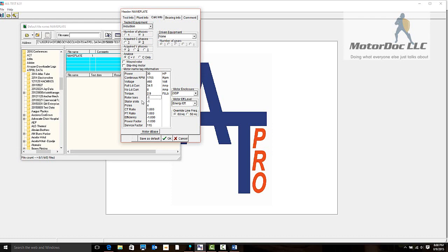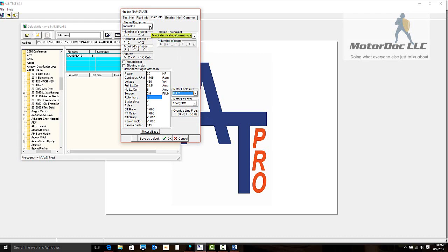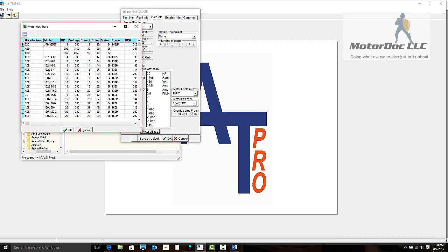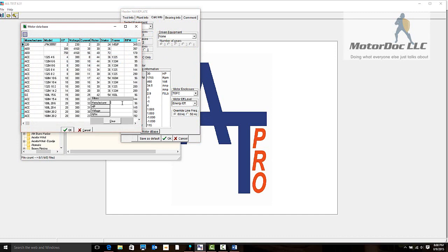Rotor bars and stator slots are critical to what we're going to do. The first thing we're going to do is select totally enclosed fan cooled, energy efficient motor operating at 60 hertz, an induction motor. If we were operating on a VFD we would select this, but in this case it is an induction machine. To find the rotor bars and stator slots, I can go to the motor database.